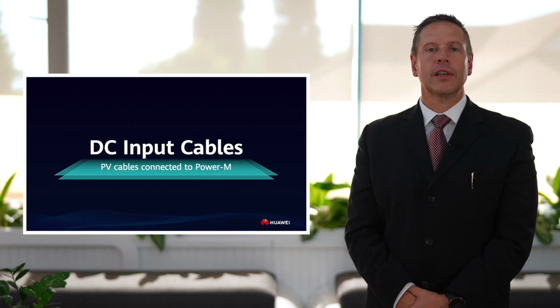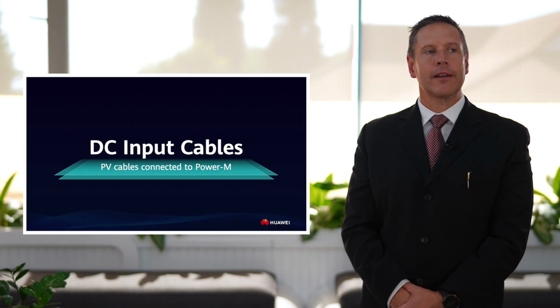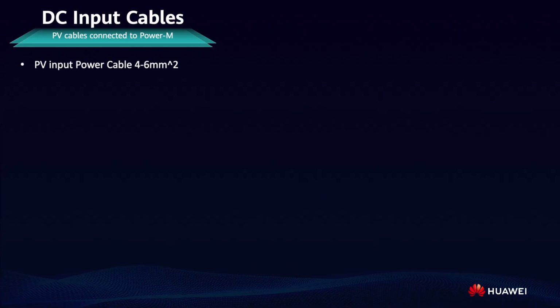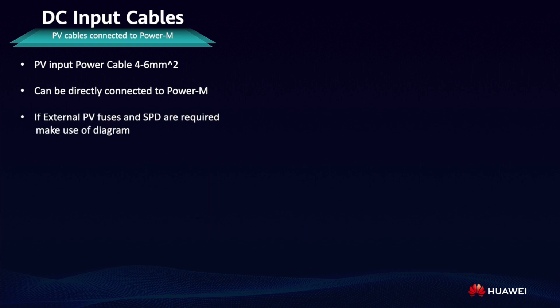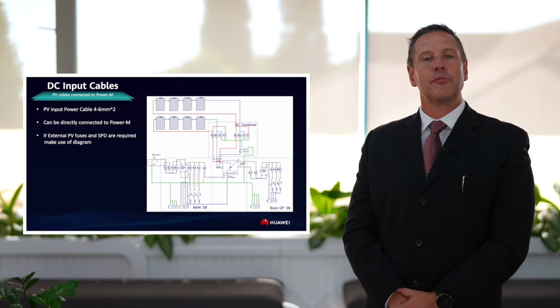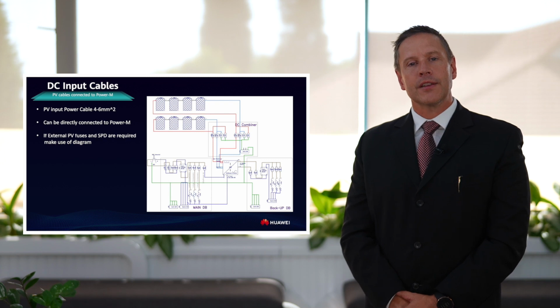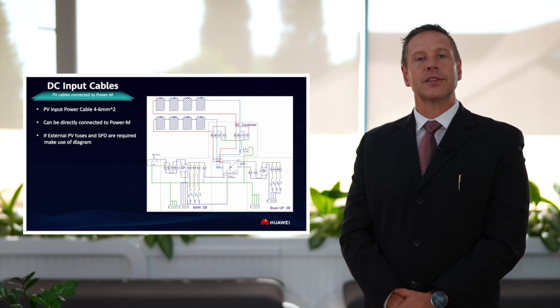DC input cables and suggested single line diagram. The PV input cables, that is 4 to 6 square millimeters, can be directly connected to the Power M. If external PV fuses and SPD are required, please make use of the single line diagram as presented. Direct connection of PV into the Power M is allowable as full protection is also built into the product.